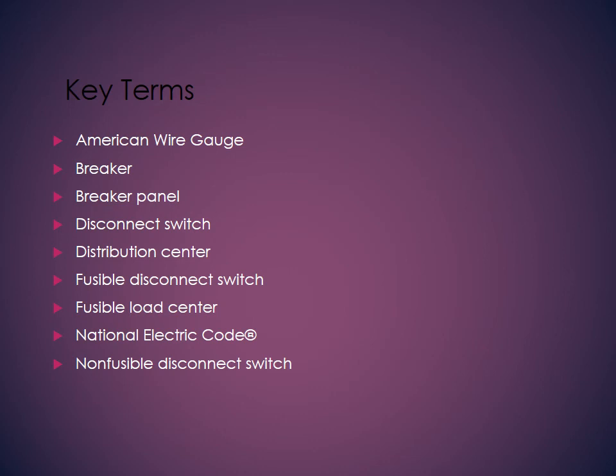So this kind of sums up what we need to know about installation. We learned about American wire gauge, and we said the code has changed from 2016 to include a 14 gauge wire. Circuit breakers are what is installed in the control panel. This is the breaker panel. Disconnect switch: you're required to have a disconnect switch on every piece of equipment. Distribution center is when you have power coming to two appliances. Fusible disconnect switch: some equipment requires a fusible disconnect switch, but again check whether a breaker is enough or we need the fusible disconnect switch. It is very similar to the breaker. So breaker and fusible, breaker panel and fusible load.